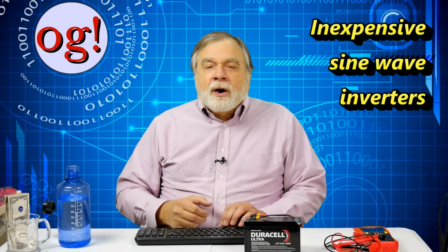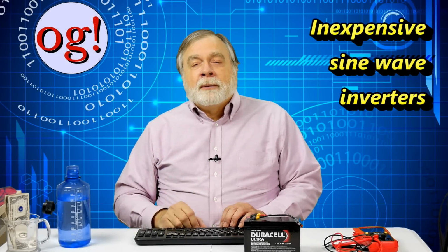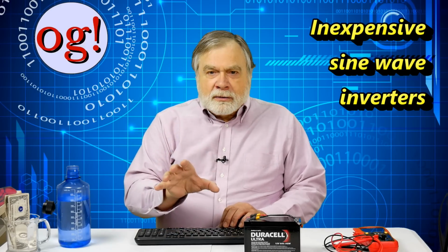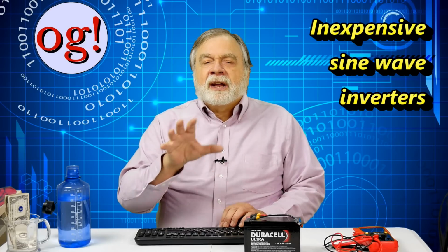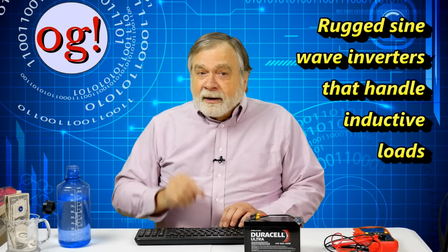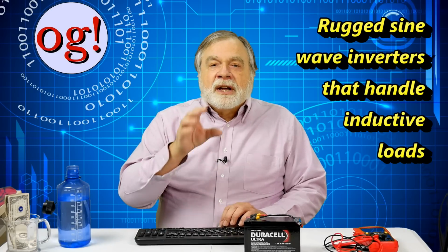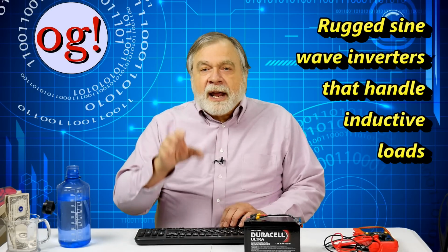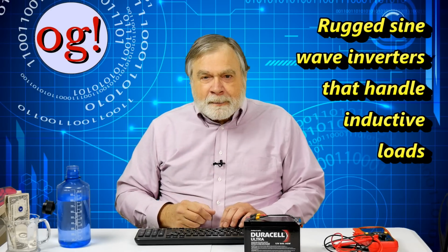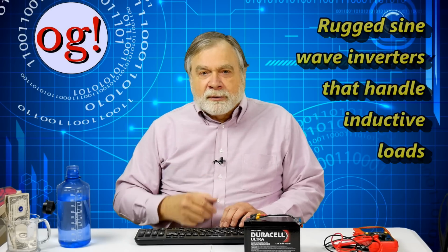Next up the ladder are the sine wave inverters, which actually do produce a much better approximation of a sine wave. This works for many loads, such as compact fluorescent and LEDs, as well as your computer and monitor. Then, and these cost quite a bit more, are the real workhorses and produce a sine wave and also can handle inductive loads with power factors significantly less than 1. You can use this type for drills and electric saws and motors.